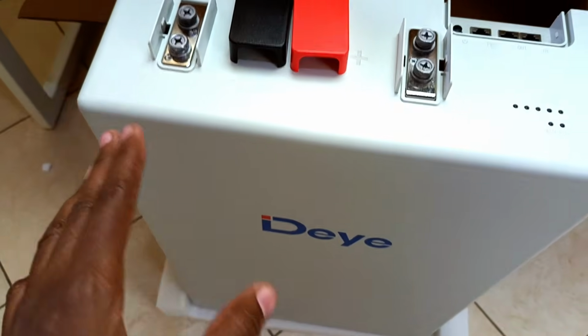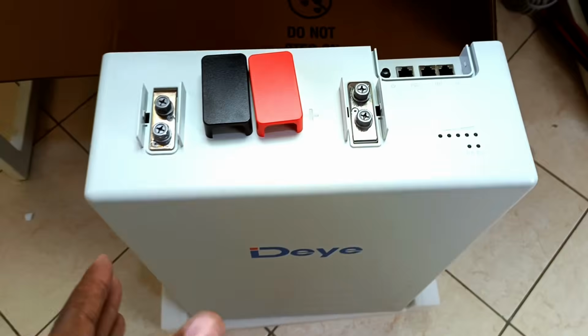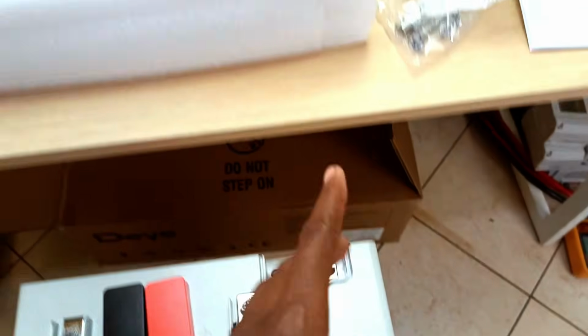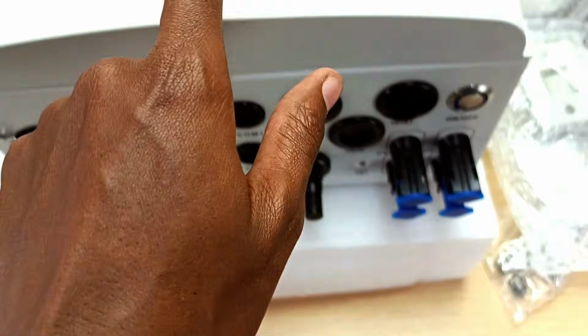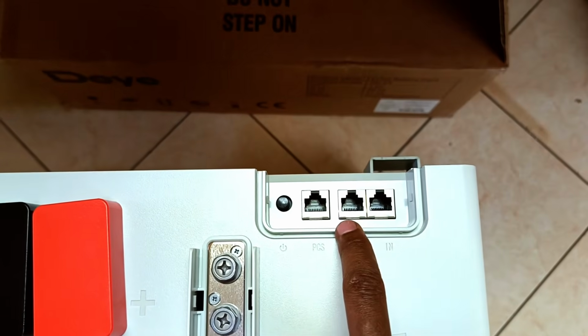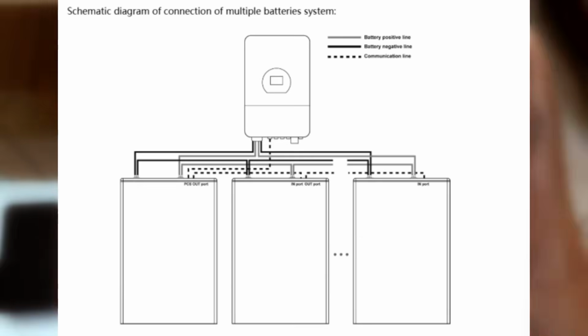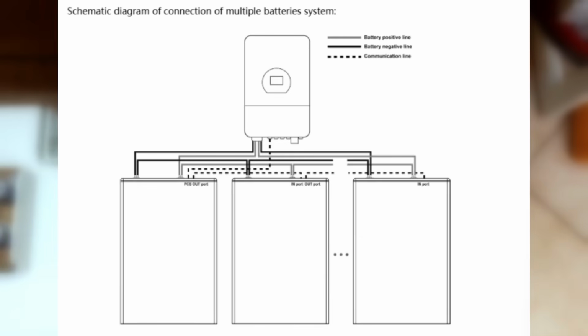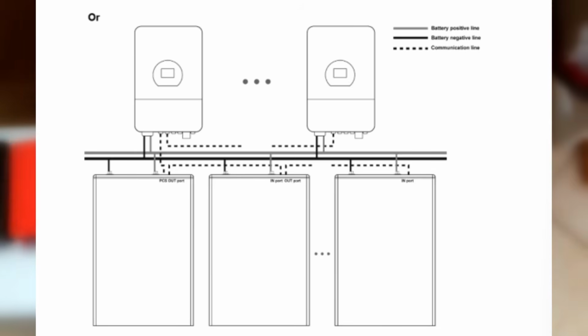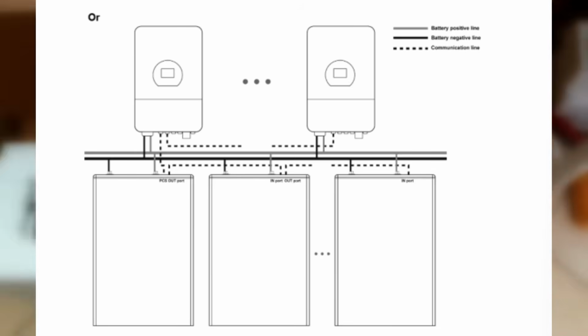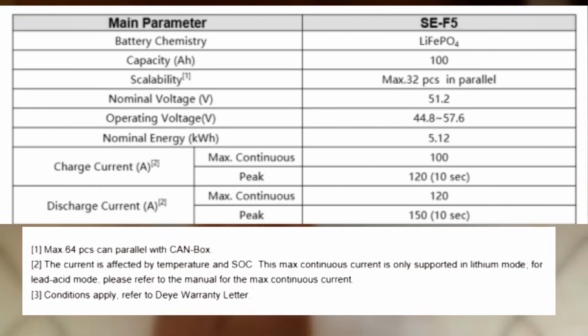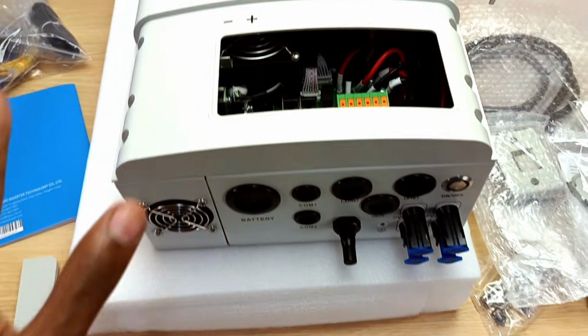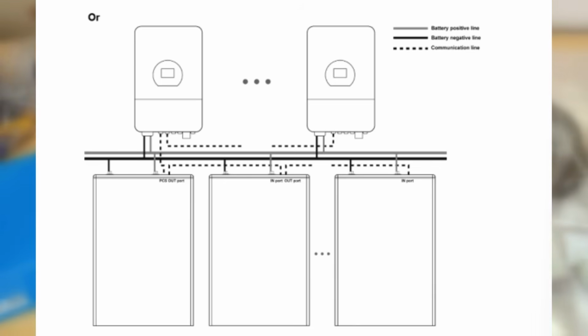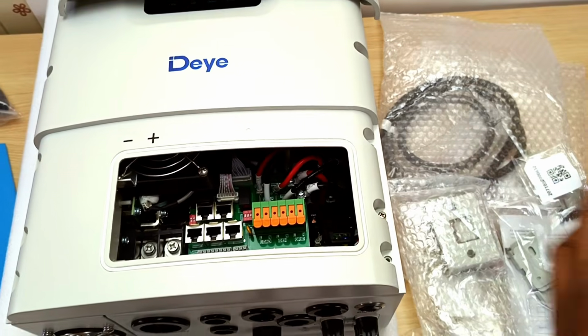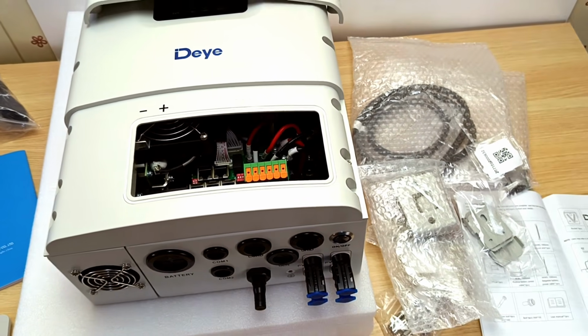You can actually install these batteries in parallel to one another. For example, I could have two batteries connected to this single inverter, and when I do that, the PCS will be connected to the inverter. The output from this battery will be connected to the input of the next battery. I hope that is clear. And when you add more batteries, you just go on connecting them like that. You can actually connect up to 32 pieces of battery. Same case with the inverter. You can actually connect this inverter in parallel with other units to increase the power output of your solar installation.